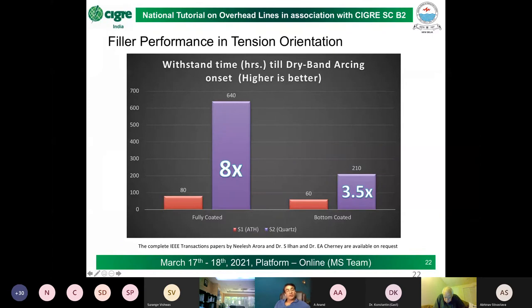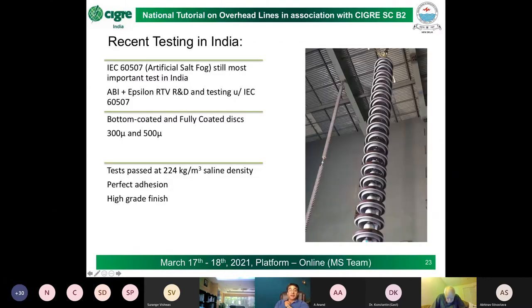To give you an idea of the ability of a coating in tension orientation to delay the onset of leakage current, we look at this graph. A bigger number is better here. For a fully coated insulator, it is 8 times longer than an ATH filled one. And for just a bottom-only coated one, it is 3.5 times longer. It is still a very, very good, very large number.